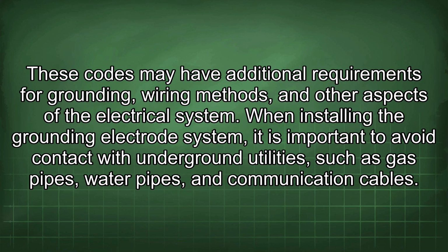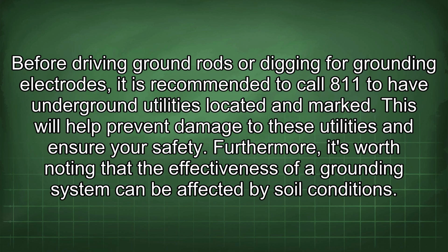When installing the grounding electrode system, it is important to avoid contact with underground utilities such as gas pipes, water pipes, and communication cables. Before driving ground rods or digging for grounding electrodes, it is recommended to call 811 to have underground utilities located and marked. This will help prevent damage to these utilities and ensure your safety.